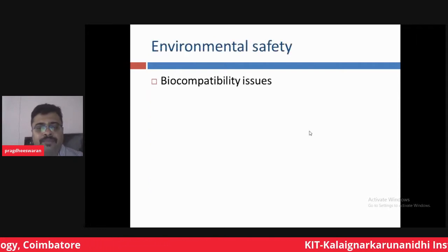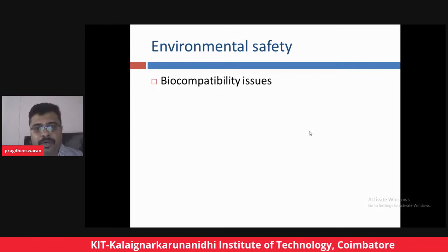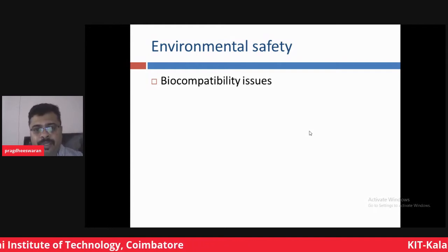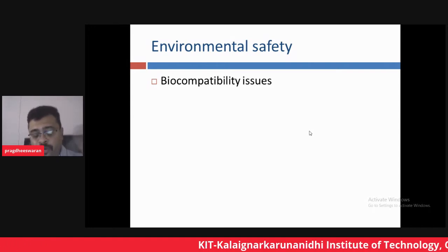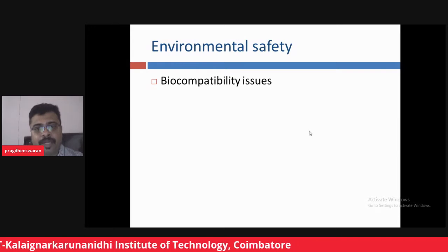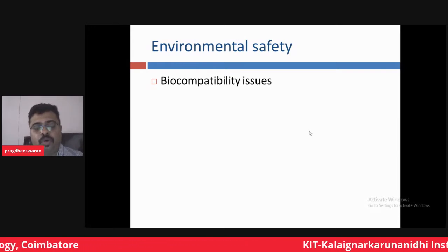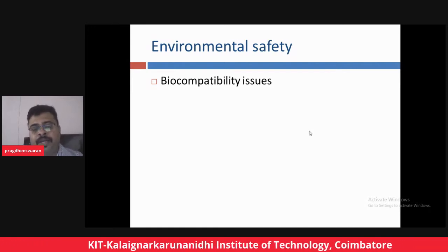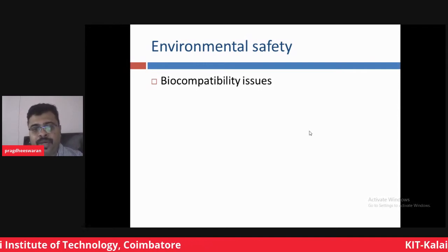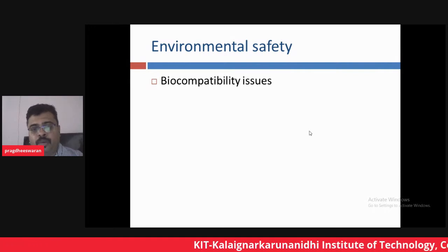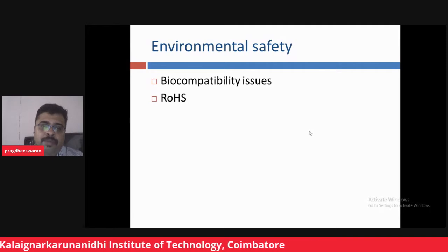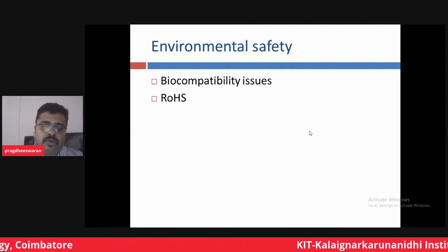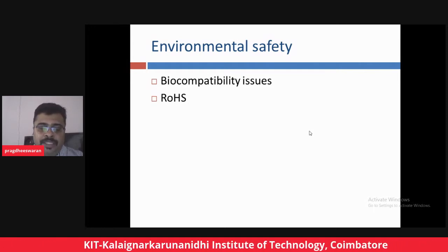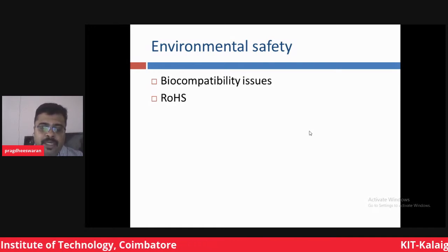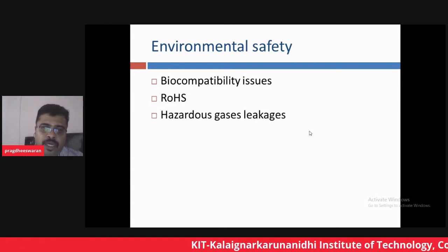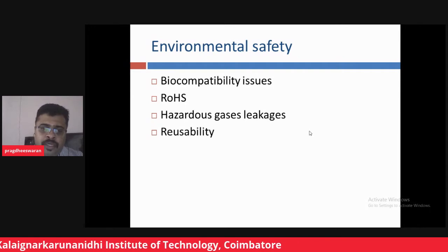Environmental safety, we basically classify as biocompatibility issues, which is where we take equipment and service the equipment. After the service, we throw the equipment out, right? Maybe we can say that's condemning the equipment. When you condemn the equipment, a proper methodology needs to be followed for medical equipment. Even a needle syringe destroyer has to follow a certain protocol to condemn the item. Even a syringe, which carries viral elements, causes issues with respect to the environment. So those things come under environmental safety. Most medical equipment is constructed out of electronic systems, so the usage of restricted hazardous substances on the electronics PCBs, RoHS PCBs, is very important. So that is what is discussed under environmental safety, and hazardous gas leakage and reusability.